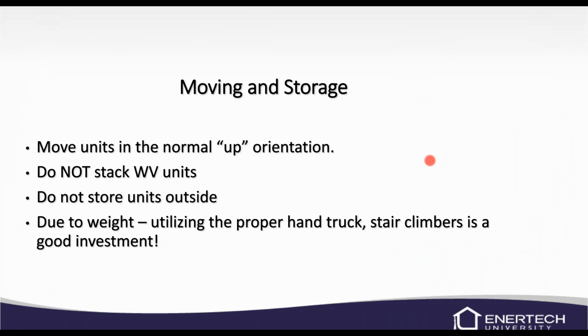So moving to storage, the unit needs to stand in the upright position at all times, just like a refrigerator or something like that. There's oil in that compressor, and we need it to be there when the compressor starts up. So don't stack the WV units. If you've got two WV units in a mechanical room, don't put one right on top of the other. You can put them on racks, one above the other. But again, like I mentioned earlier, that load pump and three-way valve are at the back top of the unit, so you may have to take the top off the unit and work on there. So we recommend a couple feet so you can get in there and work on it.